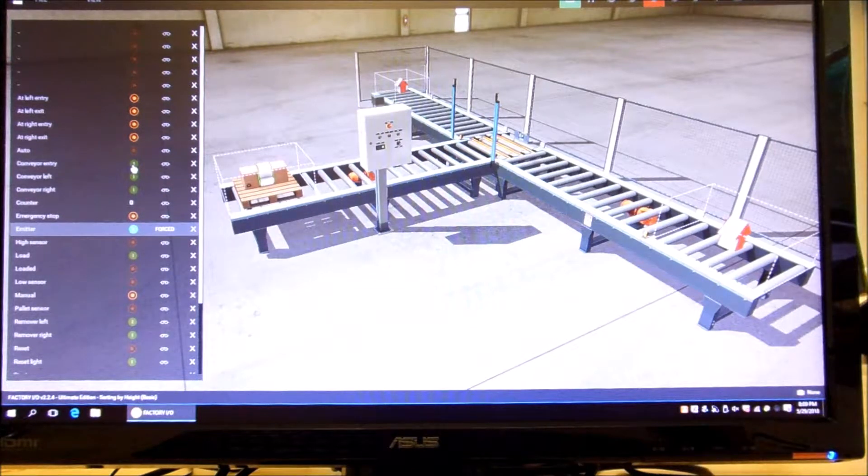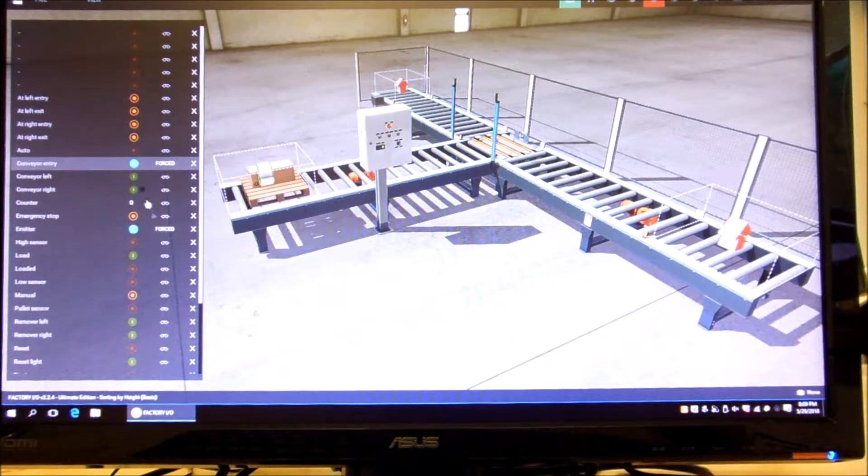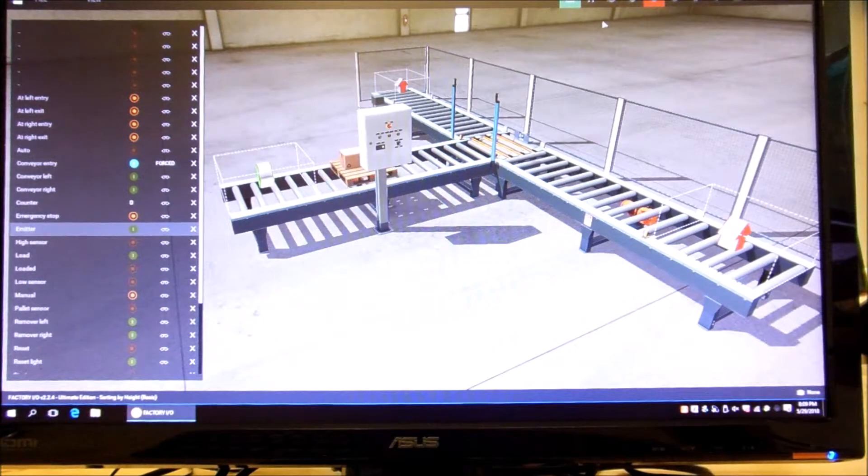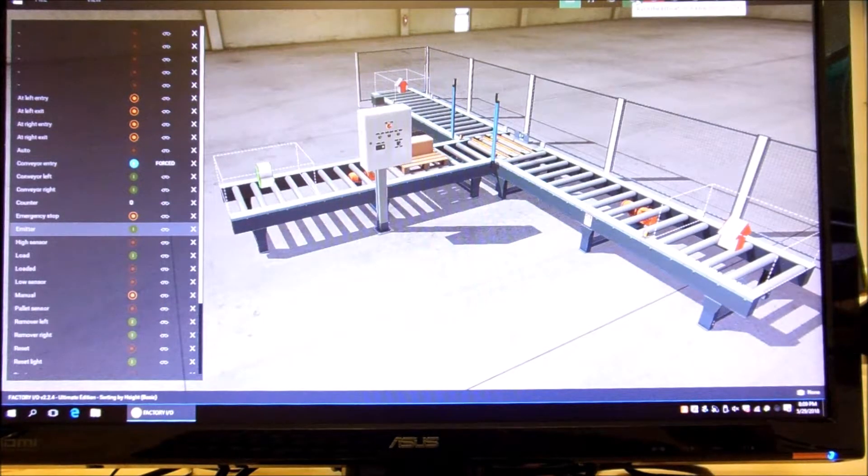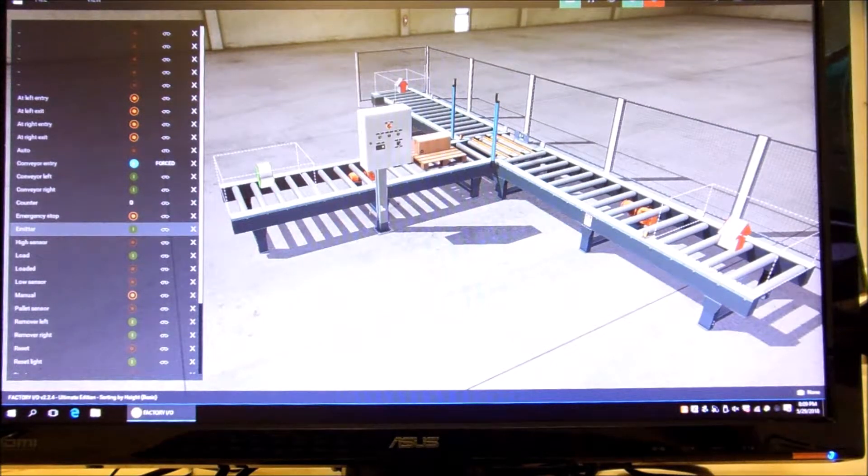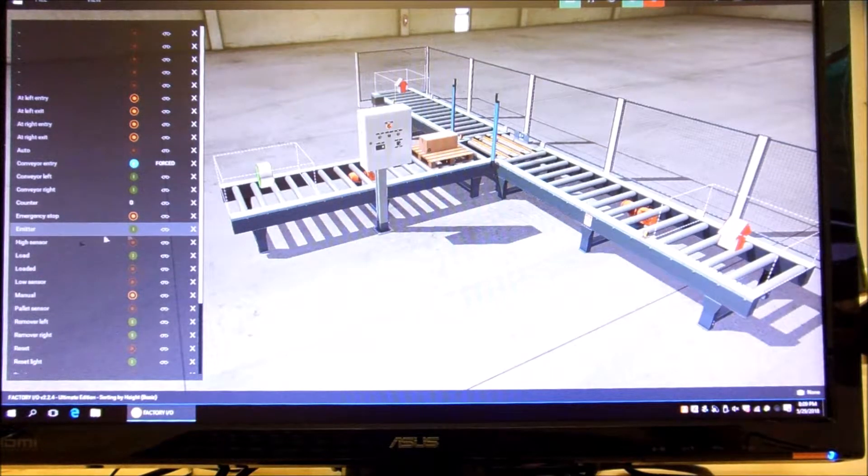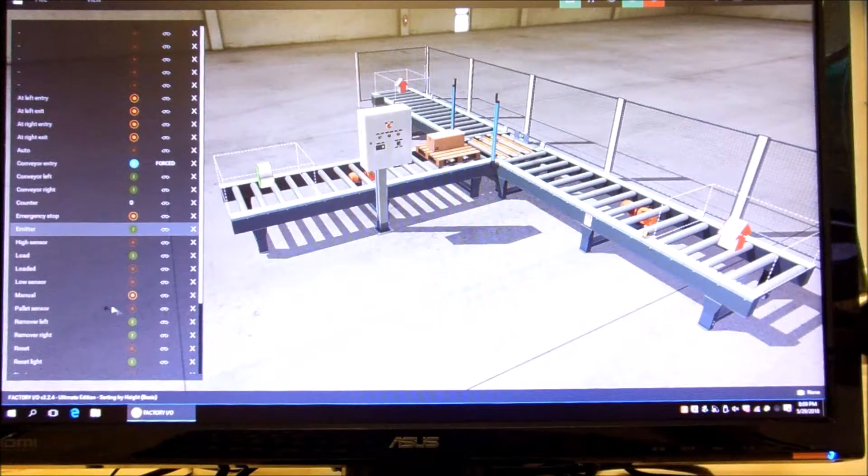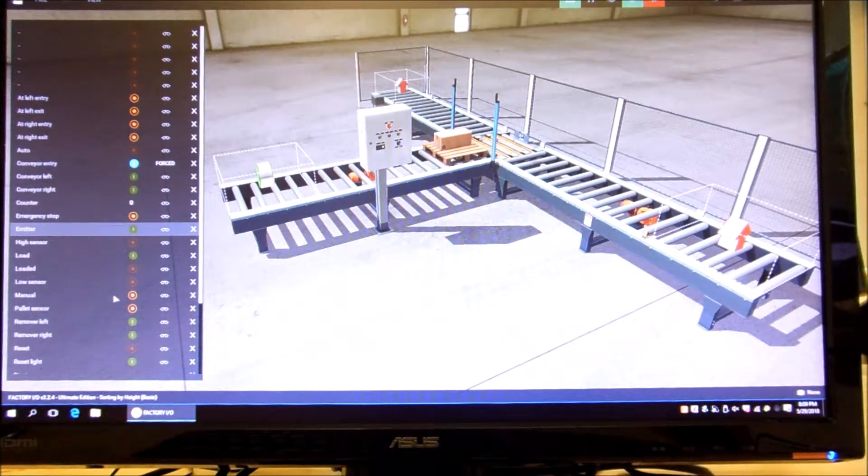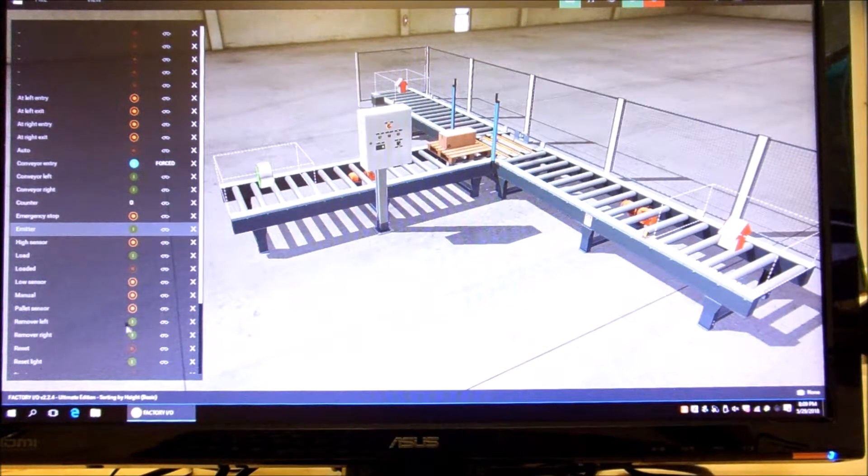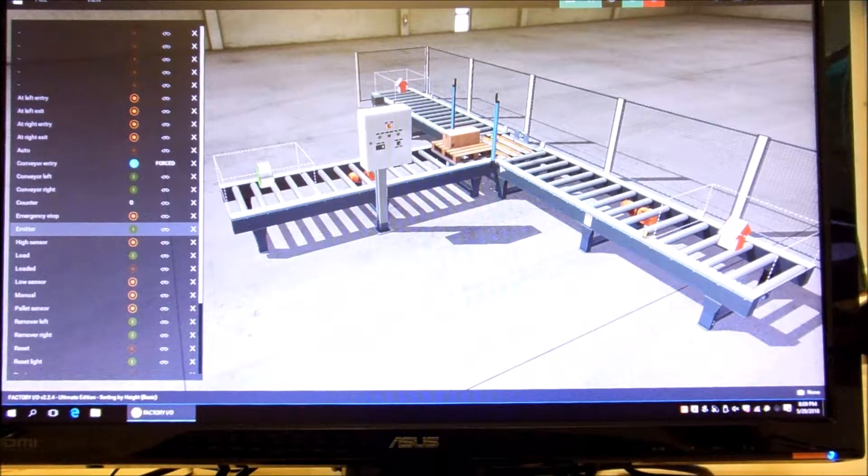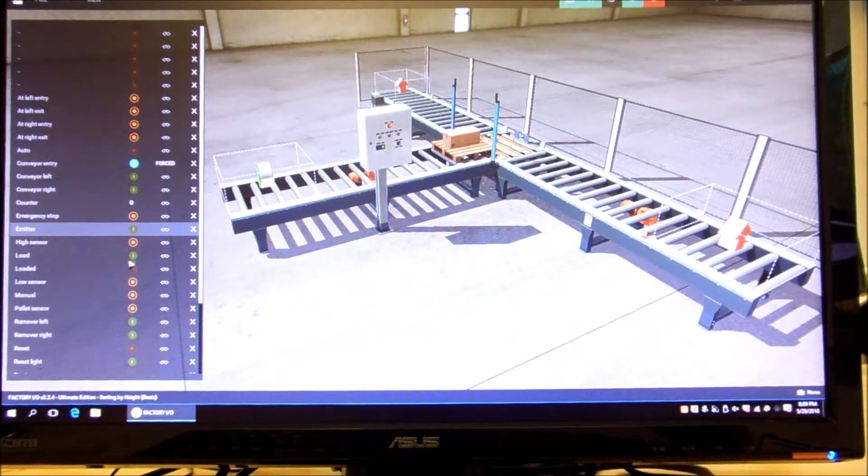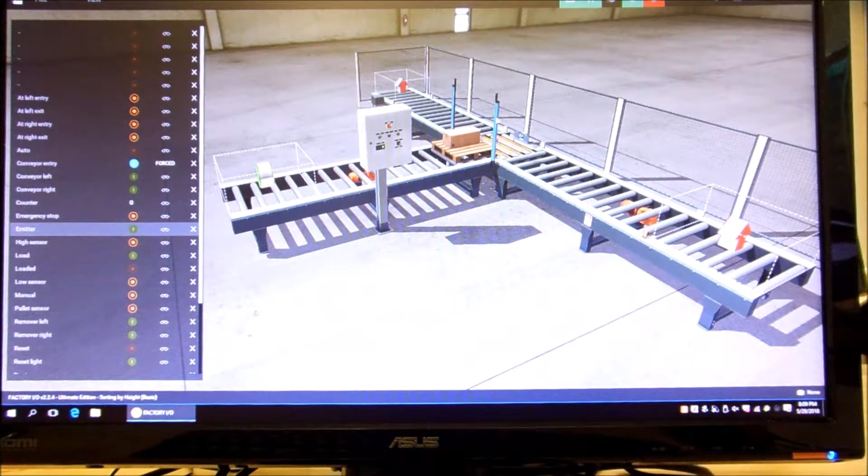I'm going to put it in conveyor entry and it's going to move. Now I'm going to turn this... Now as it gets down here, if I hit this clock it's going to slow it down. Now it's going really slow motion, so I want to look at the sensors. And when I'm looking at this, right now this front edge of the pallet, you can see the pallet sensor goes high. And then right there, and I'm going to pause it, both the high sensor and the low sensor went high.